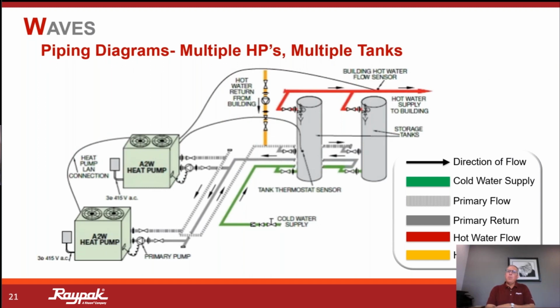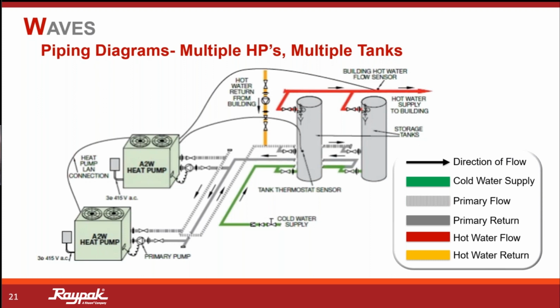And here's an example of a piping diagram. And we are working on getting some higher quality images. But again, it gets a little bit busy with these multiple heat pumps and multiple tanks. But again, very easy because we're used to this. We're used to that reverse return principle. So we're bringing our cold water supply in. We're feeding that tank. Hot water going out of the tank as it's heated.